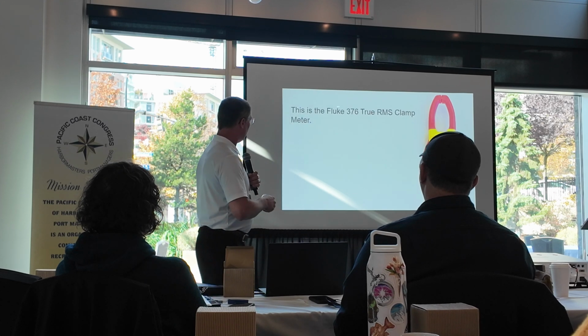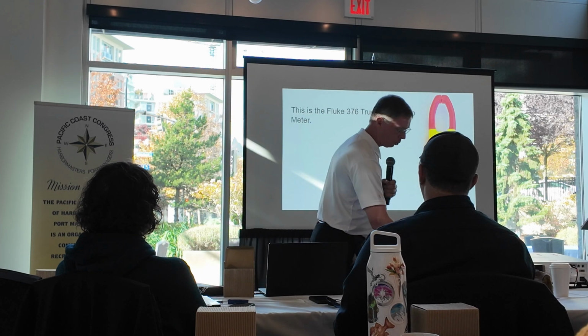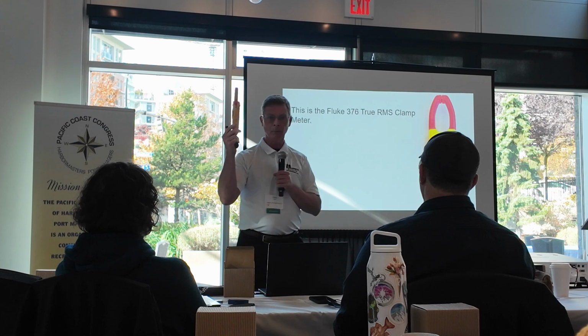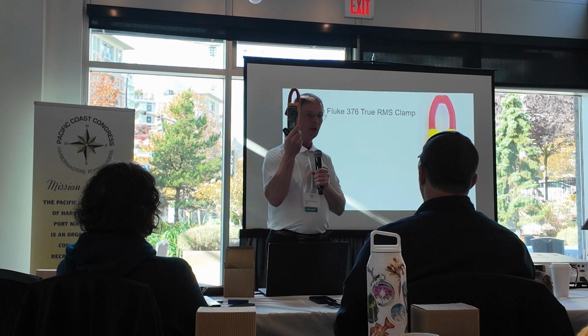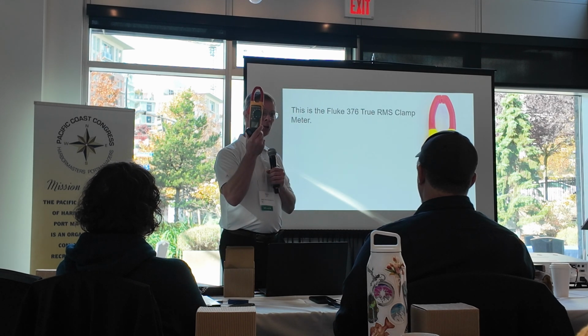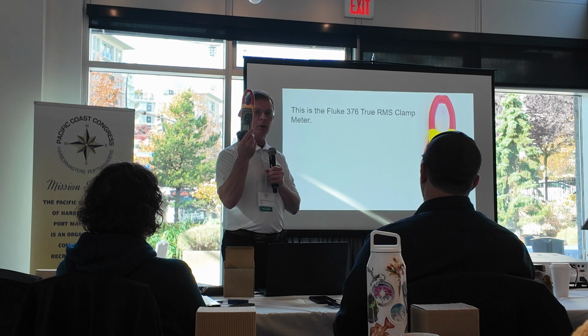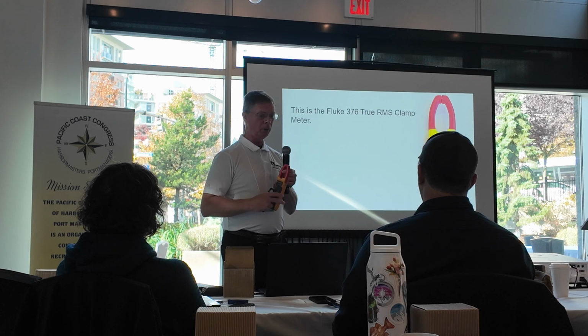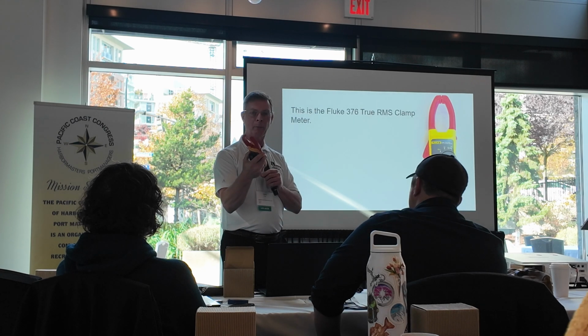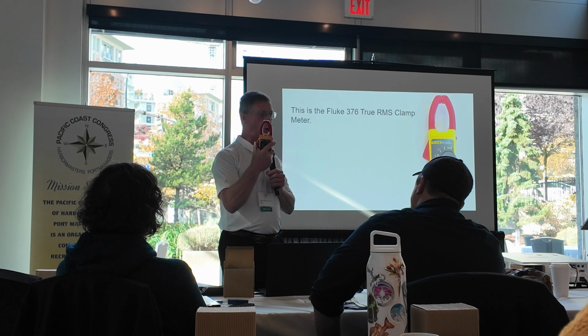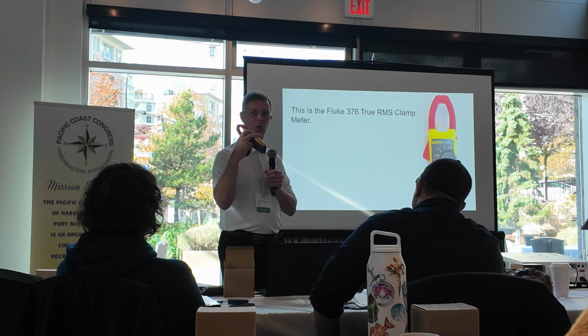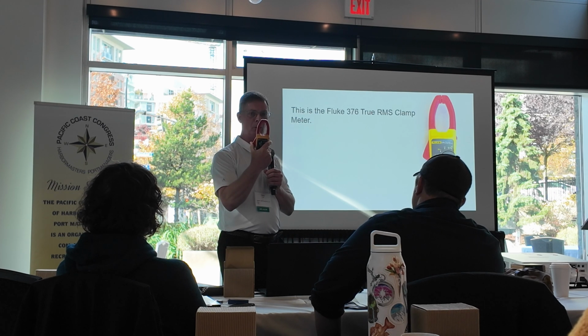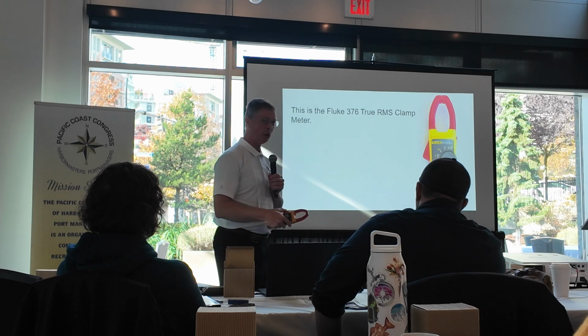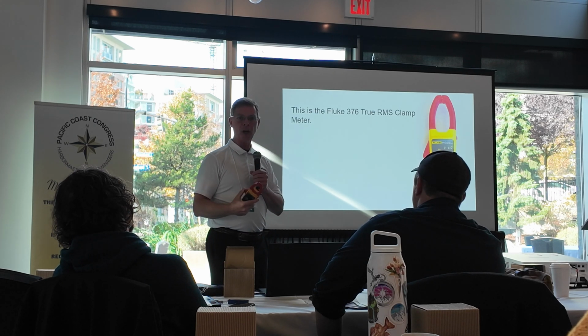And I just showed you this Fluke, which is about a $700 meter, by the way. It's a very, very nice meter. But you can't use this in what I'm doing if you're going to physically measure it, and I physically measure things all the time. This is not sensitive enough. Once you get down to about a quarter of an amp, 250 milliamps, this will go to 0. So if you use a meter like this and start measuring leakage currents everywhere, I just get zeros everywhere.